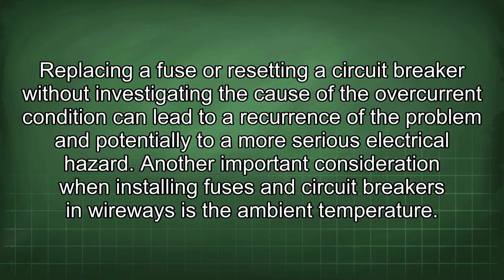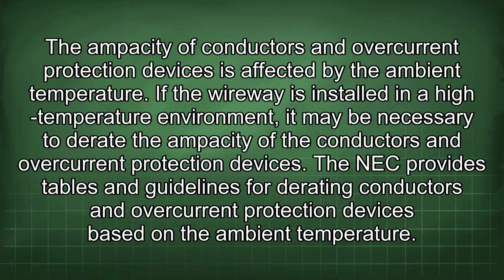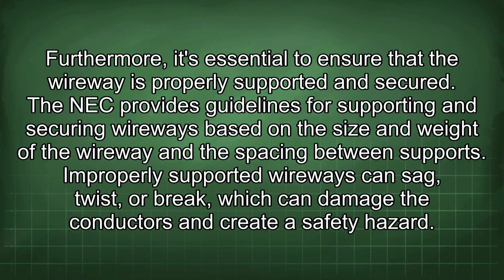Another important consideration when installing fuses and circuit breakers in wireways is the ambient temperature. The ampacity of conductors and overcurrent protection devices is affected by the ambient temperature. If the wireway is installed in a high-temperature environment, it may be necessary to derate the ampacity of the conductors and overcurrent protection devices. The NEC provides tables and guidelines for derating conductors and overcurrent protection devices based on the ambient temperature. Furthermore, it's essential to ensure that the wireway is properly supported and secured.